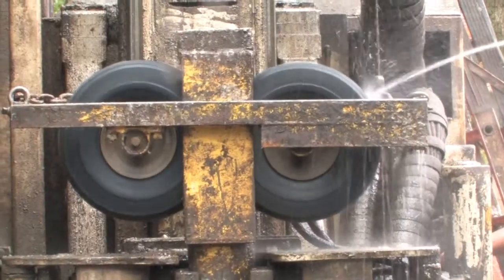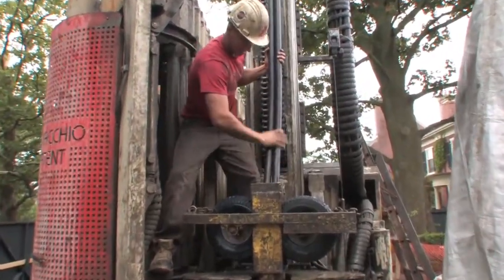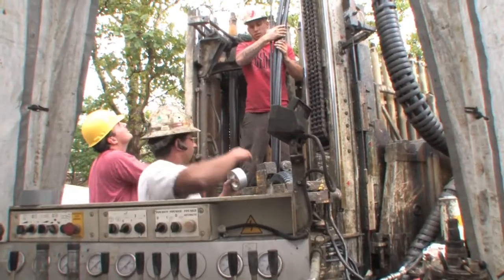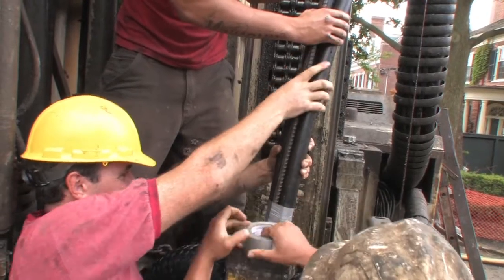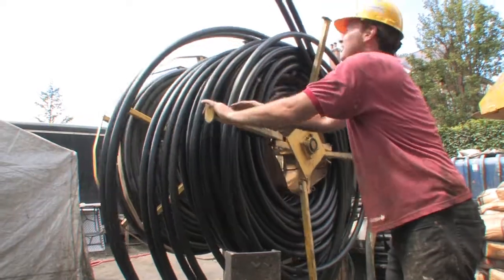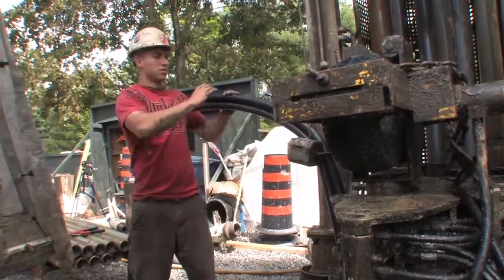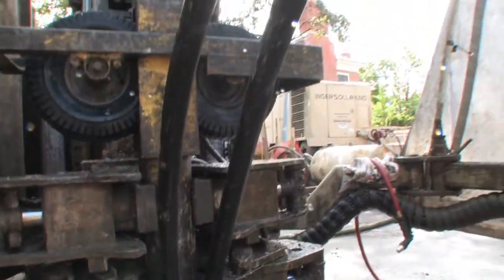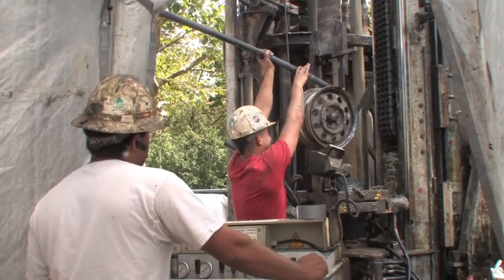Once the holes are drilled, they are fitted with a specially constructed U-shaped plastic pipe that sends liquid down to the bottom of the tube and allows it to return to the surface. This is called the loop. Every vertical drill hole will have the two tubes from this loop sticking out of the surface. This final tube is the grout delivery tube.